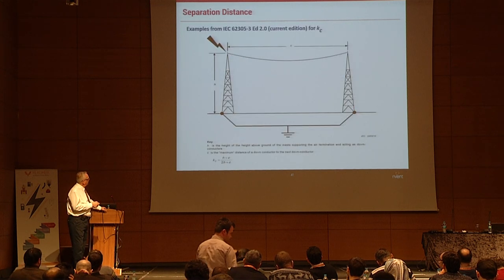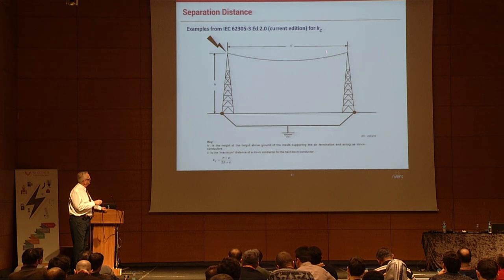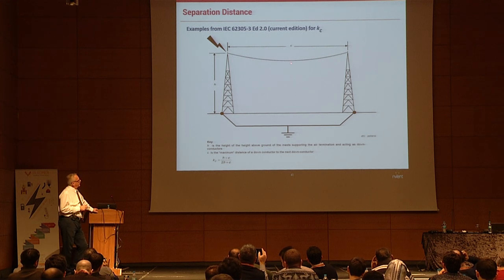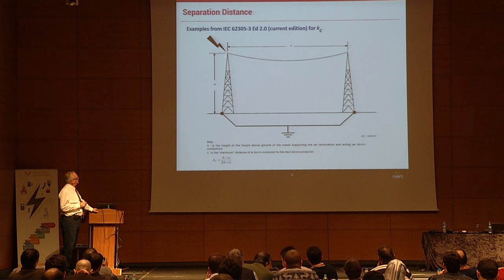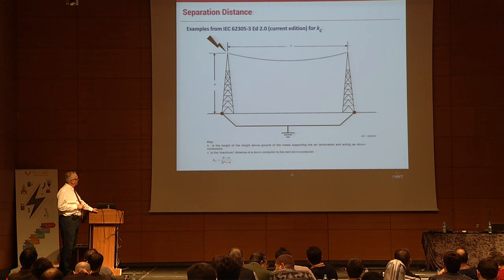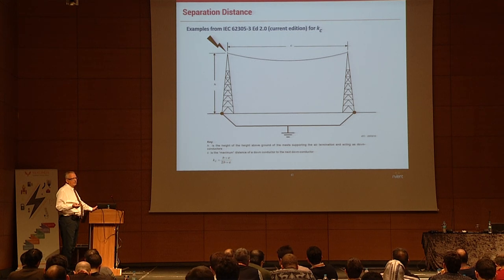The Kc calculation uses the height of the structure, the distance between the two points, and the point where lightning strikes. For example, if H is 20 meters and the distance is 40 meters, you have 60 meters divided by 80 meters = 0.75, giving a Kc value of 0.75. If the strike is not exactly in the middle, more energy may go one way than the other, which changes the Kc calculation.